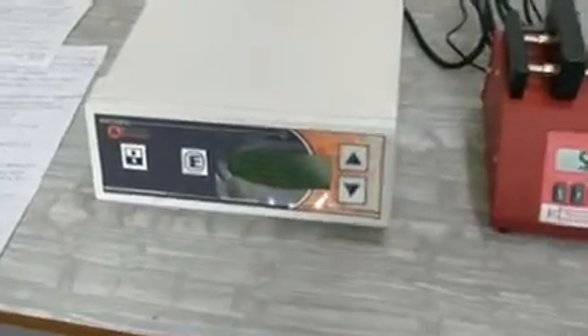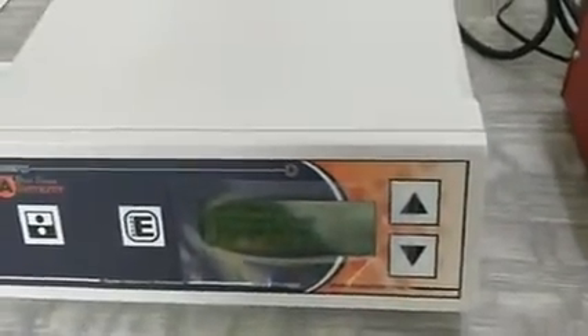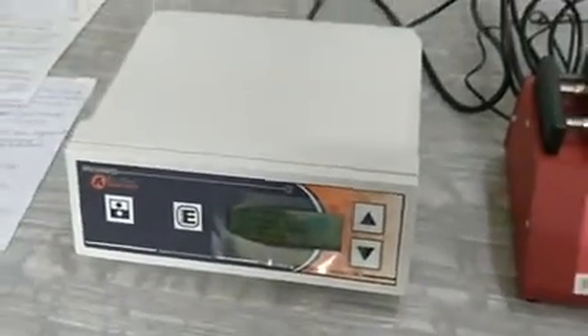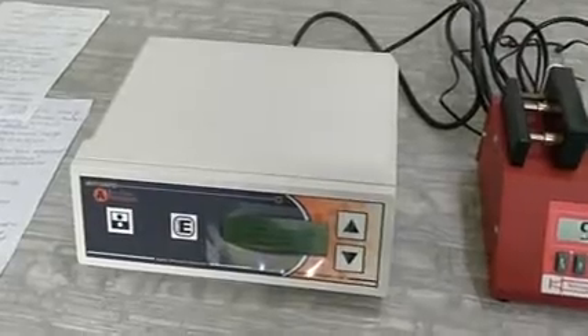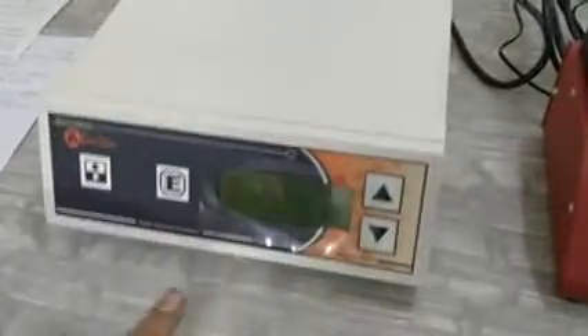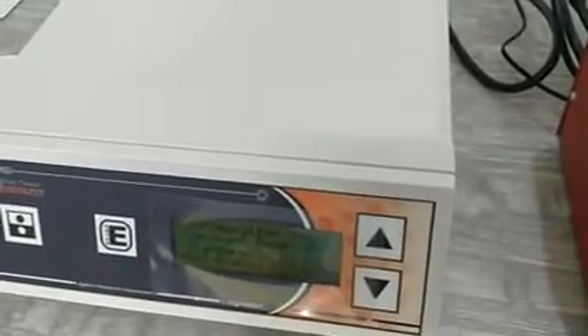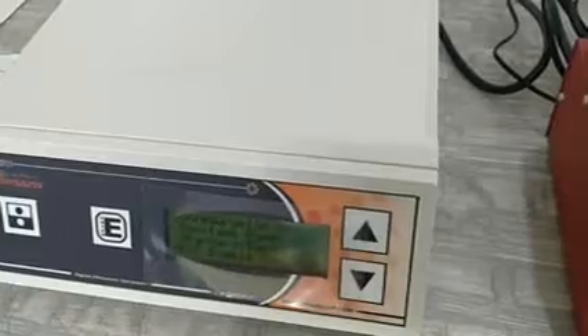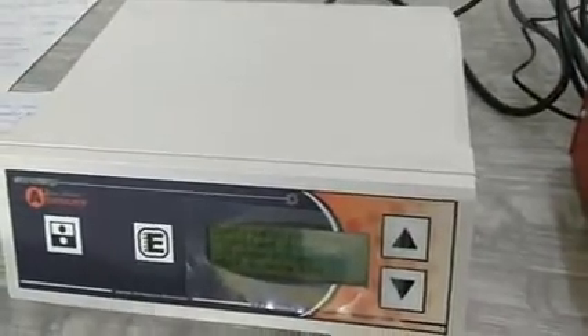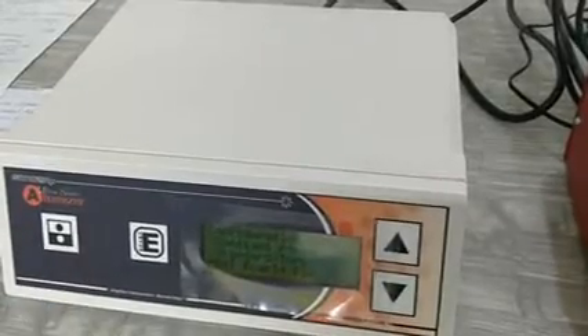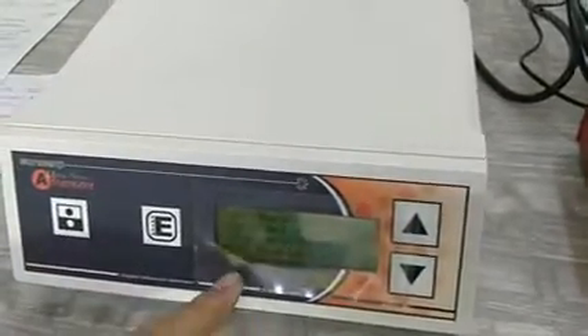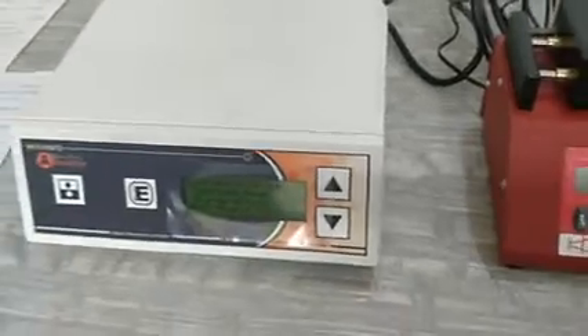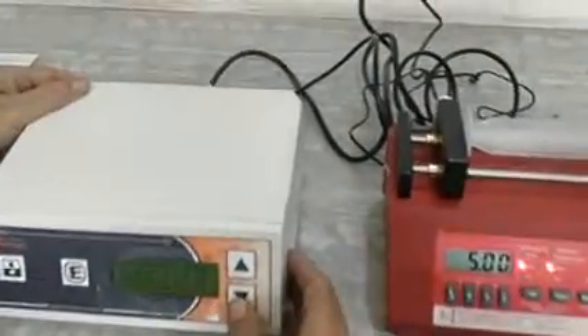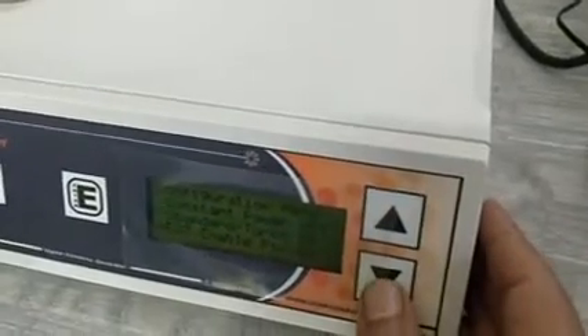In many applications the generator is connected to an external device, and if you want to control start or on/off from the external side, you can do that. Pin number 4 is the external enable pin, and pin number 5 is ground. We are keeping external enable high, meaning if pins 4 and 5 are open, we give power internally. If you want to reverse it, make external enable low, and then you can externally short pins 4 and 5 to start the generator. So this is used only if you want to control externally.